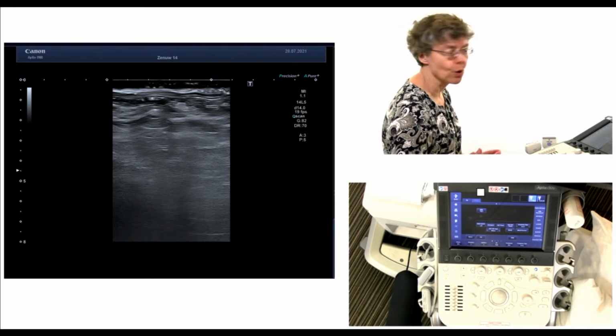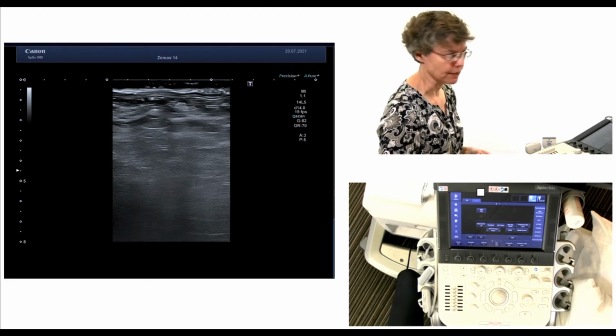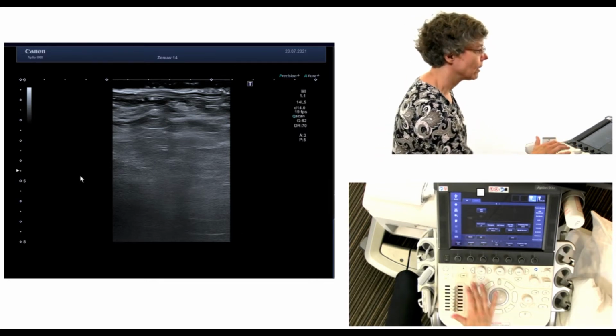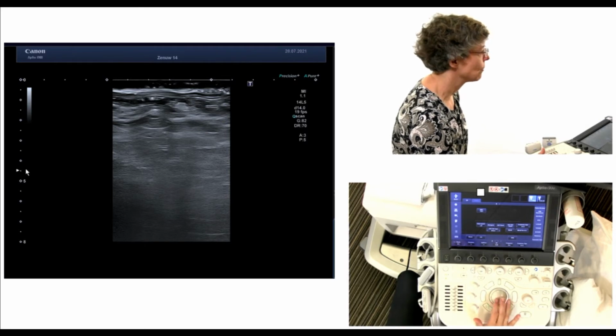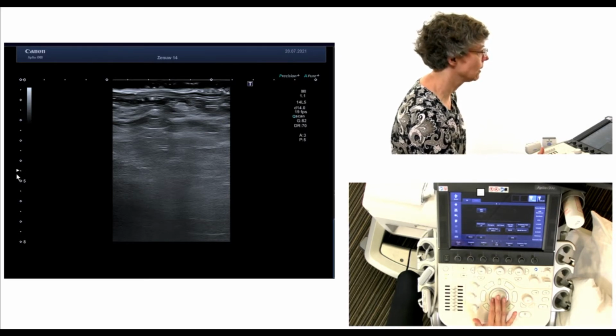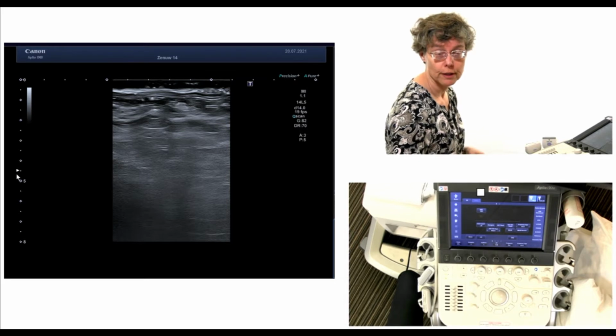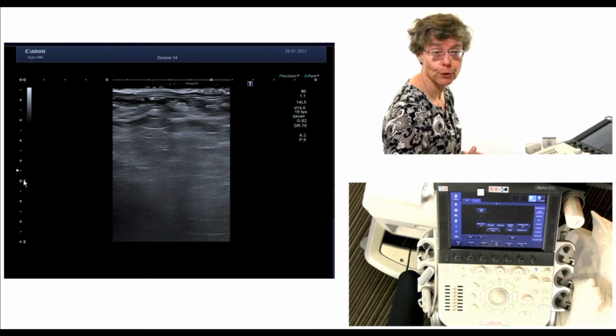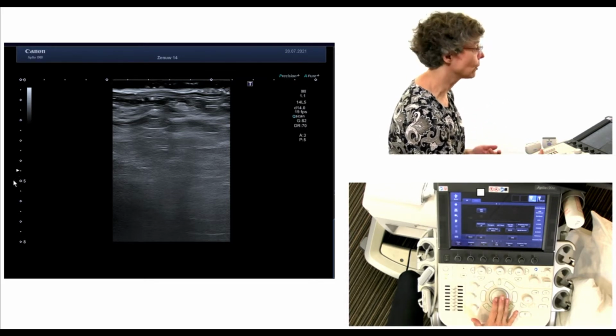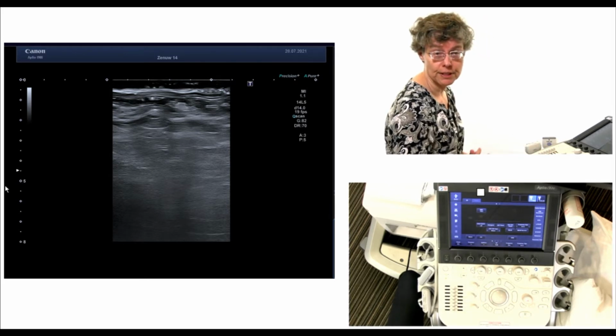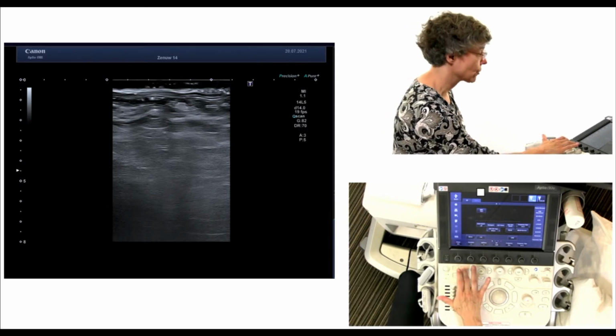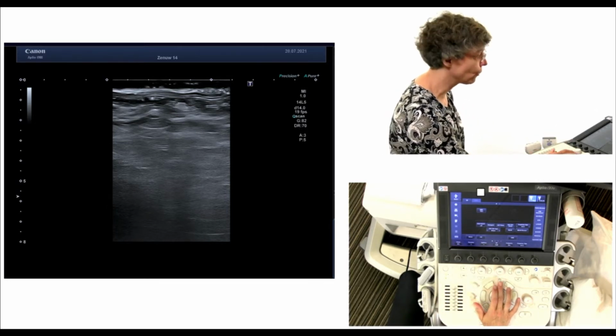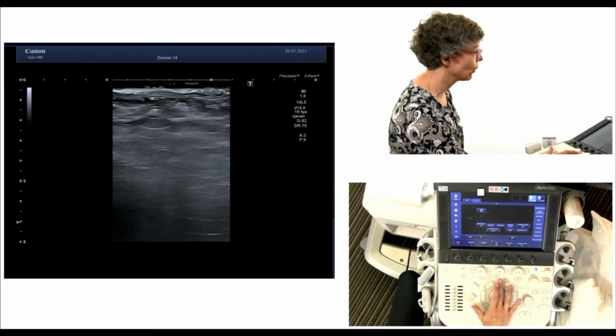Maybe you think, I want to see something that is at 7 centimeters deep. Well, there's a couple of other things that you need to adjust right there, because here, this little arrow here is the focus. This machine is set to have a single focal point. Maybe it can do multiple, but we're going to use this one focal point right now. But if something is at 7 centimeters depth, you need to adjust this. So I'm going to turn off the arrow here. The focal zone or point can be switched with this little wheel. And we're going to go to that 7 centimeter depth.